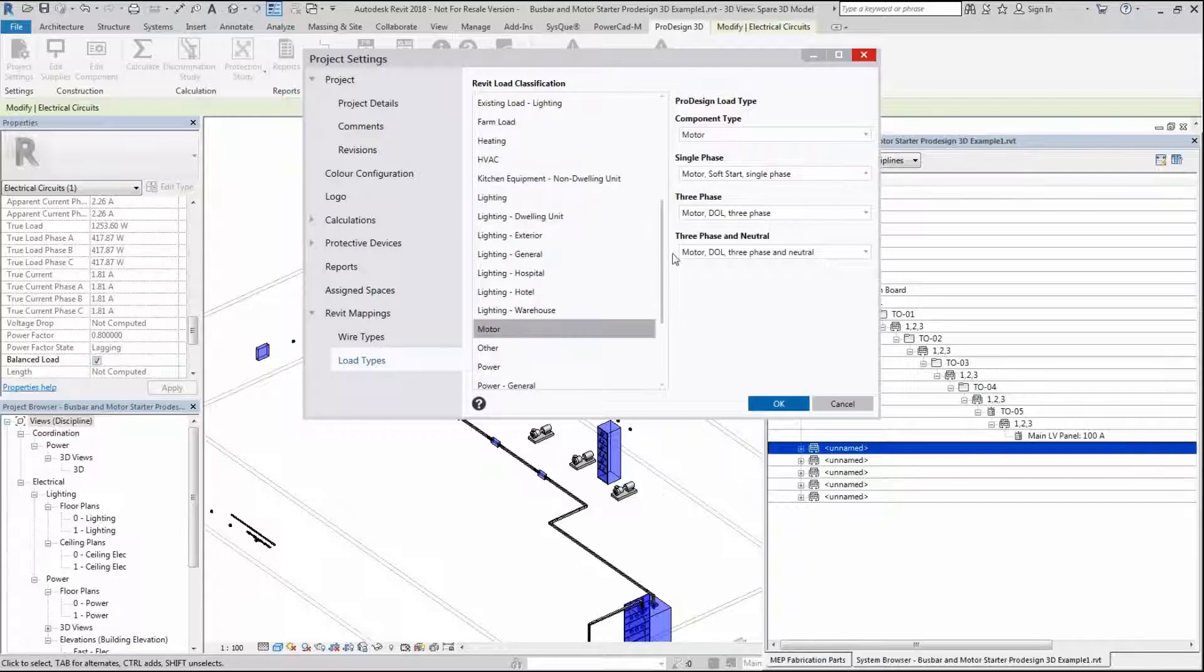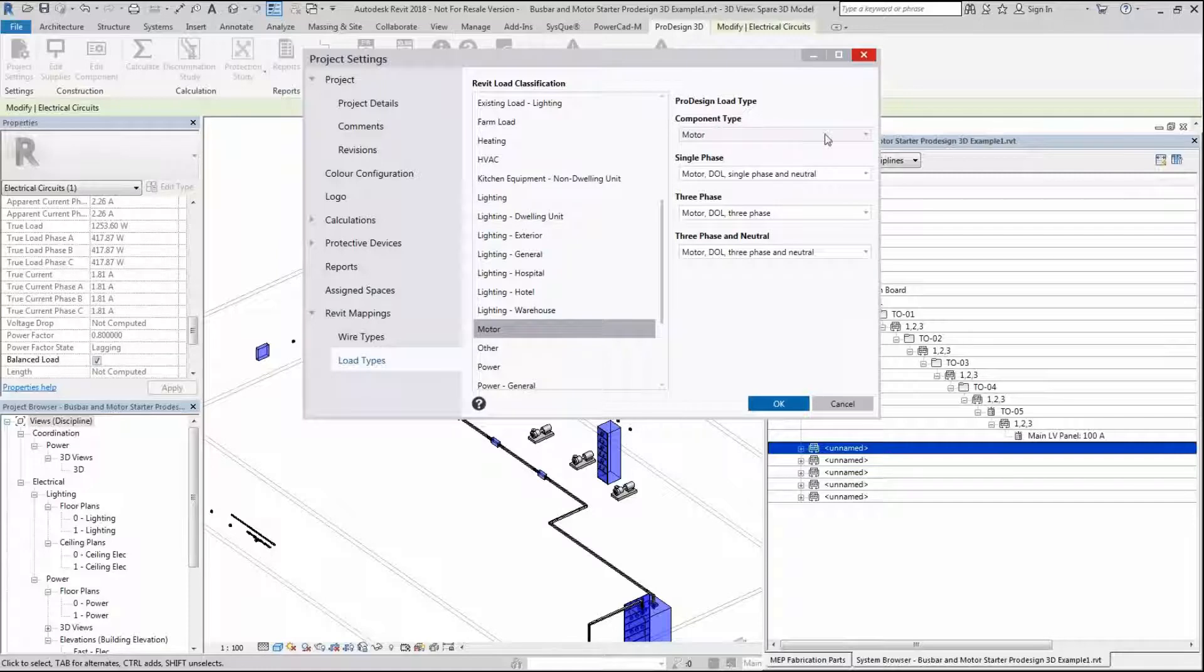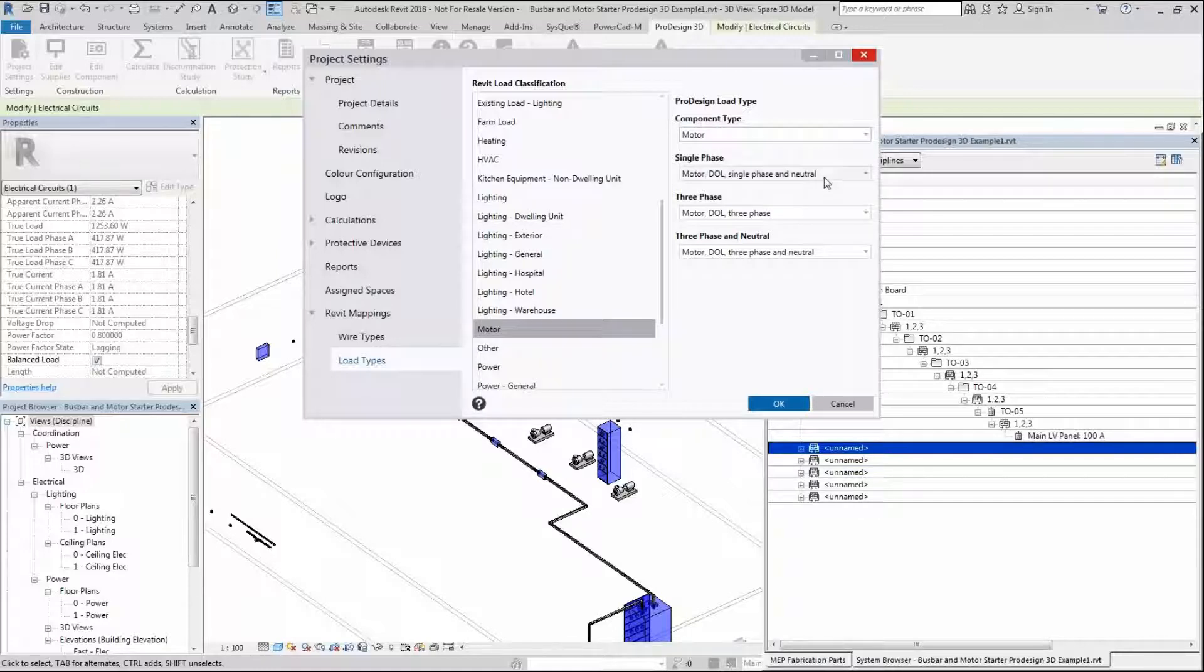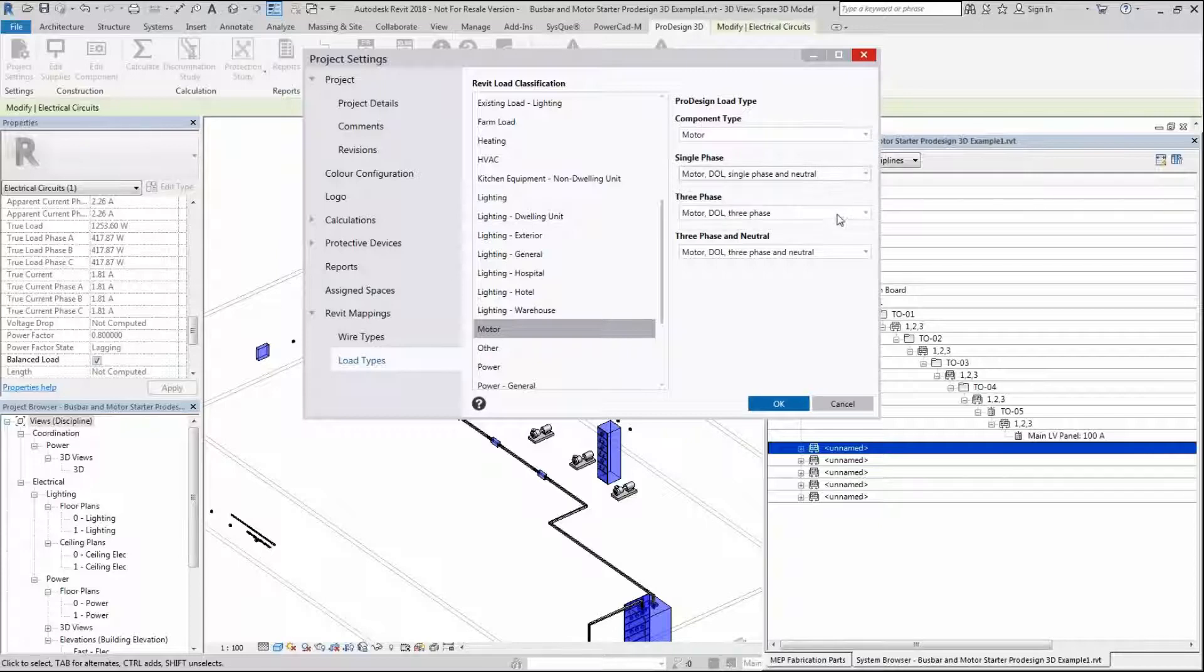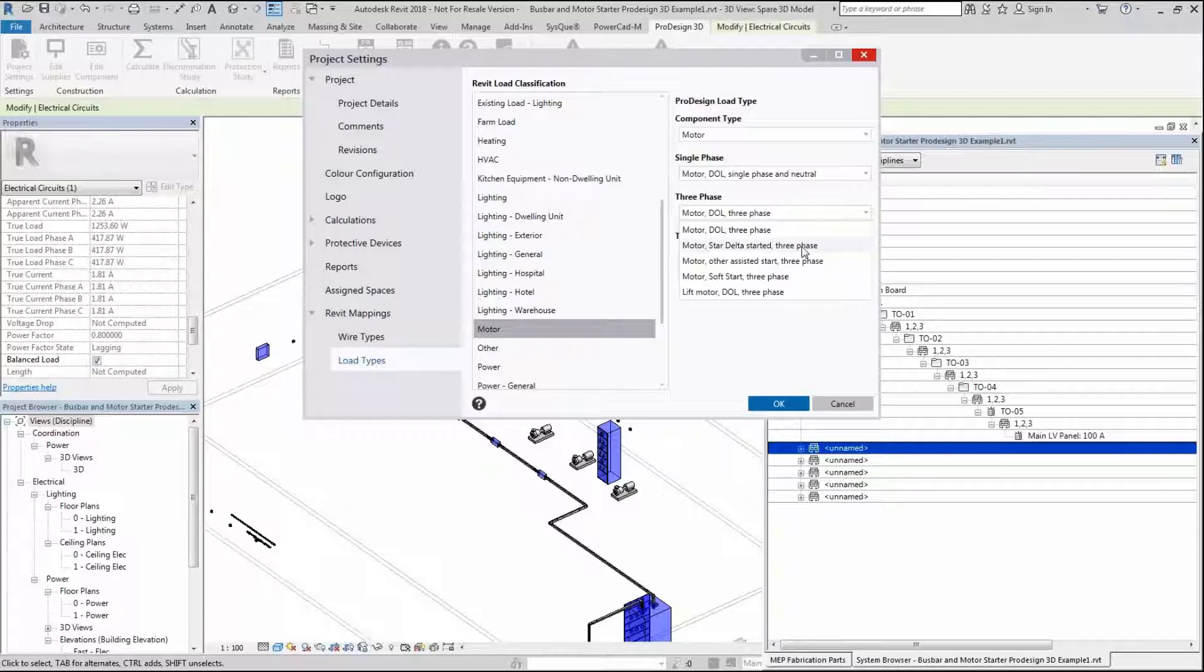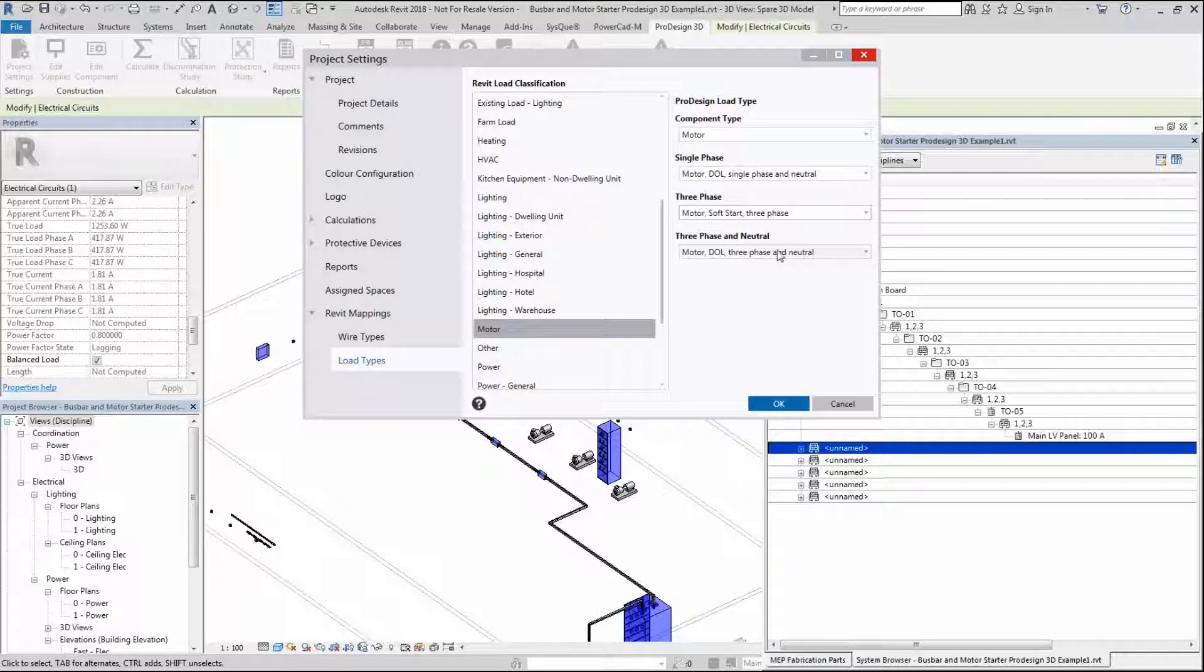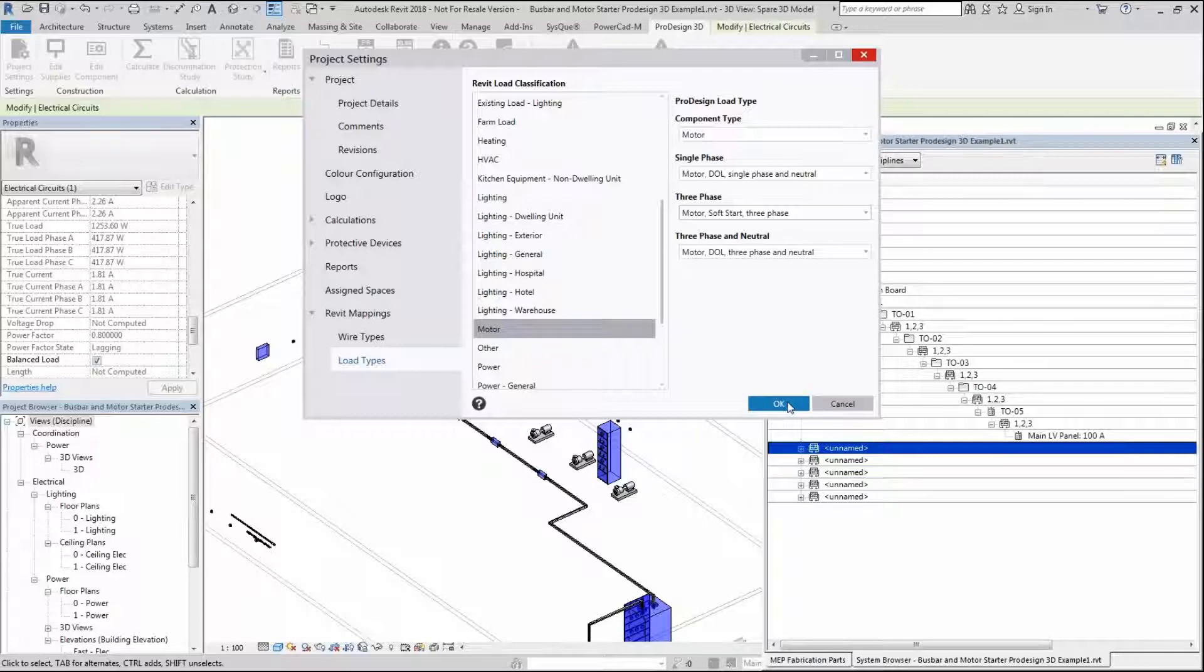For a motor, I've set this up to say motor component types is a motor. If I want to change this to a load, I can. You can change the type of arrangement. If you want a three-phase motor to always be started as assisted start or soft start, we can do that. We're going to do that in this scenario and then set up the three-phase neutral as a DOL just for this instance.